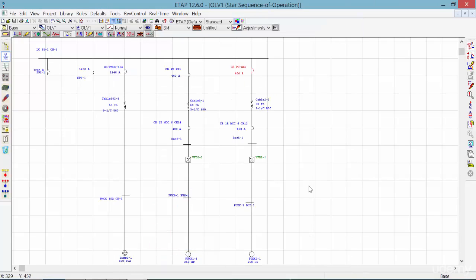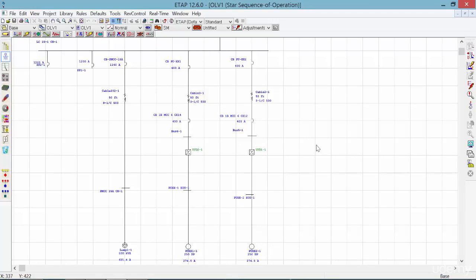Let's click on OK. So what has been done here is, since these two branches for each 250 horsepower pump have the same characteristics, the breakers for each branch are set with the same exact settings. For the feeder breakers and the VFD breakers, we're gonna have the same settings, so we can just put the same breakers and settings for each of these breakers.